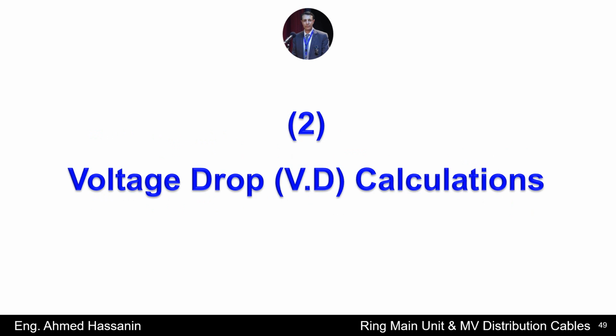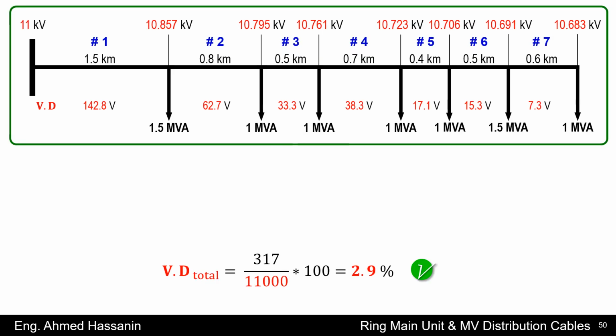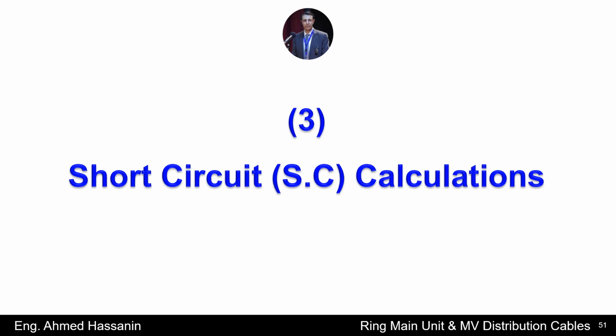In the second step of the first method, I will calculate the voltage drop. As we see in the figure, in detail and step by step, I will calculate the individual voltage drop for each part of the medium voltage cables of the ring system and the total voltage drop for the ring system. In the last step of the first method, I will explain how to know and calculate the short circuit current that the medium voltage cable can withstand at any fault or any short circuit.